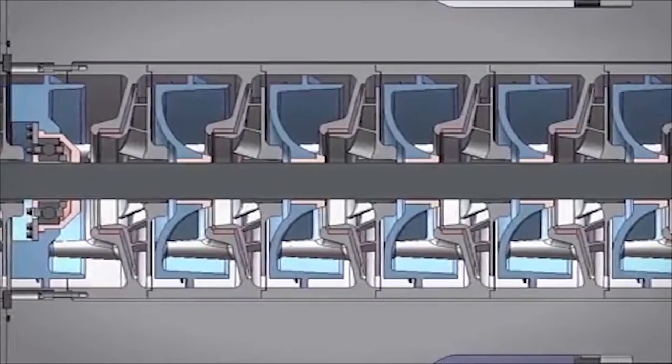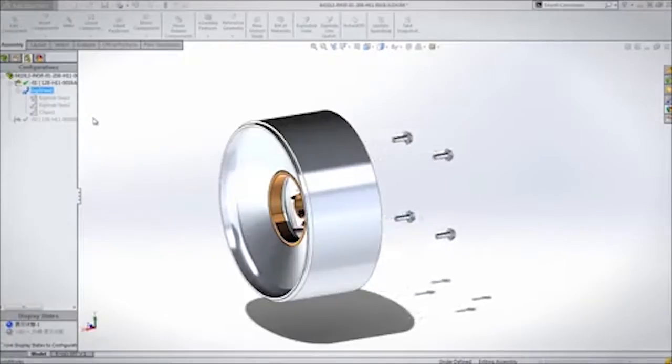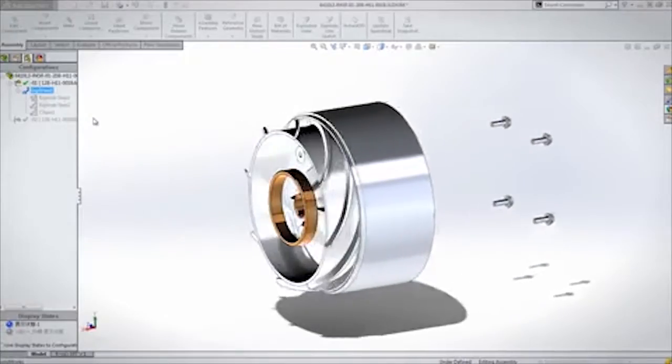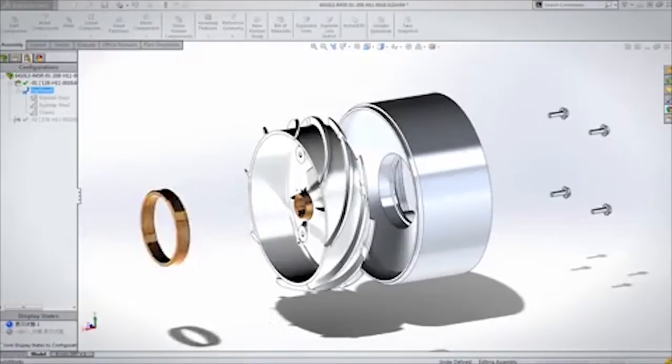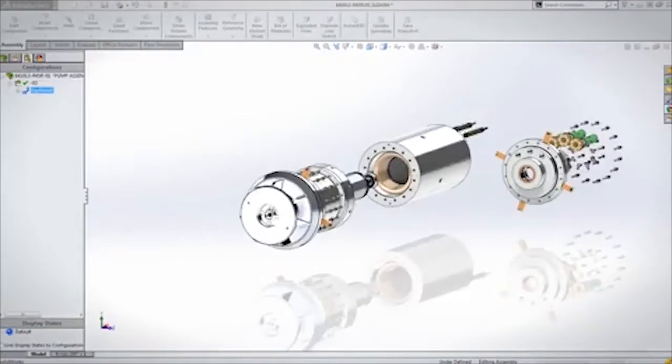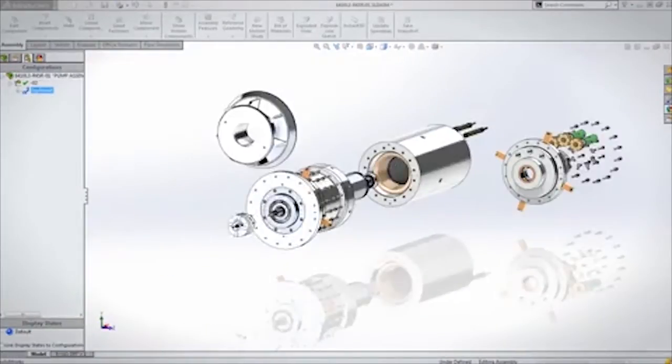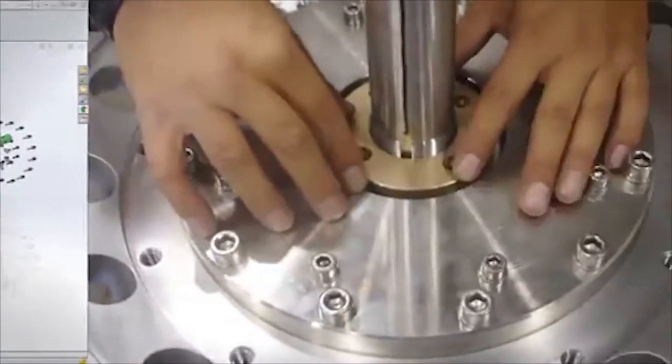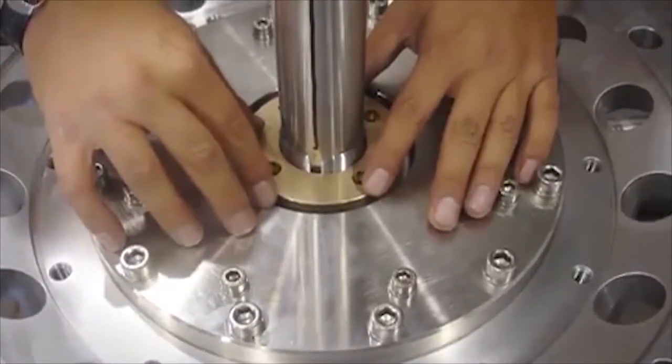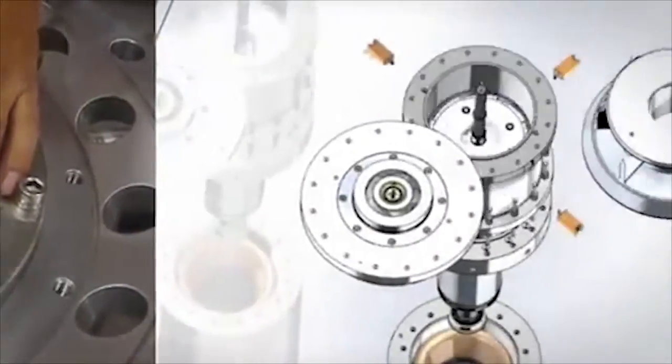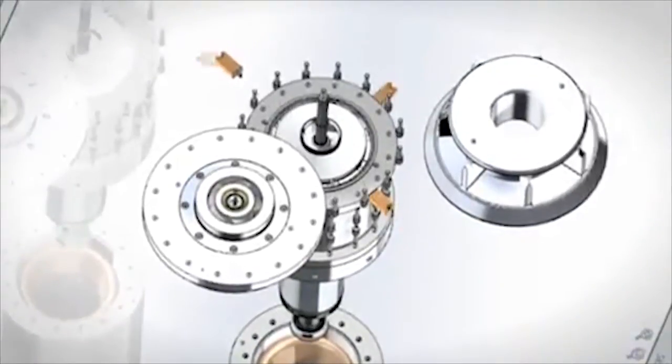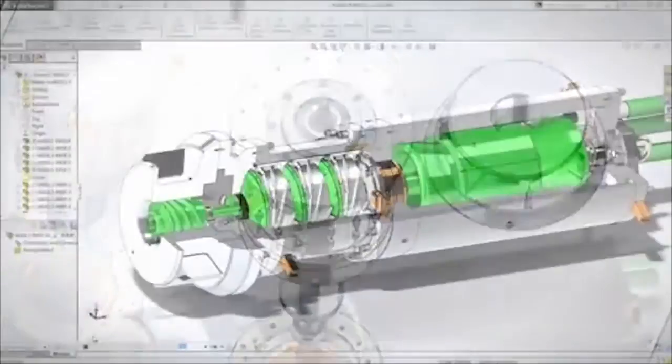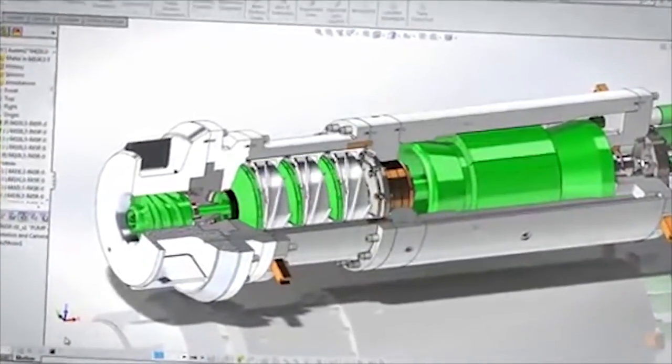The specialized machine shown in this video is a submerged motor LNG pump which operates at minus 160 degrees Celsius. It has 11 impeller stages and produces a flow of 375 cubic meters per hour and a head of 1,662 meters.